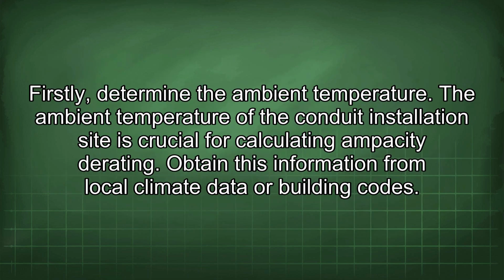Firstly, determine the ambient temperature. The ambient temperature of the conduit installation site is crucial for calculating ampacity derating. Obtain this information from local climate data or building codes.